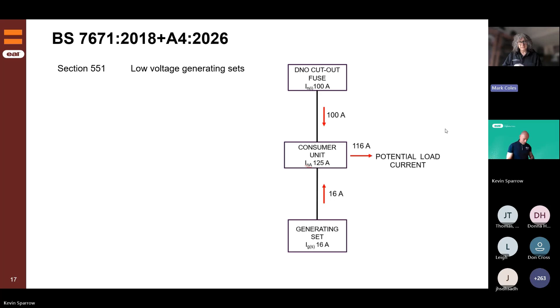But if you then add in a generating set and you add more load, you can be drawing from the middle, the consumer unit, as depicted 116 amps, but that busbar within the consumer unit might only be rated at 100. So this is a really important point: where you're adding sources, you've got to be aware of what's happening in the middle of it all, i.e. the middle being the consumer unit or distribution board, because you can, under certain circumstances, overload the assembly in there.